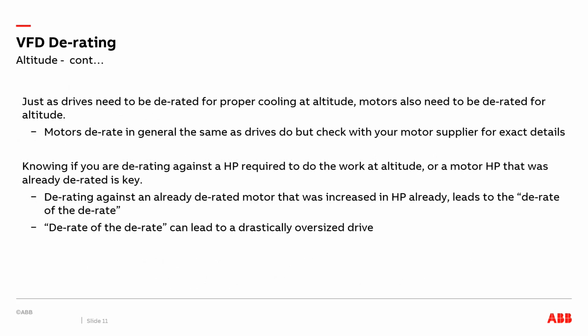So continuing with altitude here, I want to bring some motor aspects into this presentation. Just as drives need to be de-rated for proper cooling at altitude, motors also need to be de-rated for altitude. Motors de-rate in generally the same way as drives do, but I always want to say check with your motor supplier for the exact details on how they handle their de-rating for altitude. This is going to become clearer on the next slide, but I want to bring this up now.